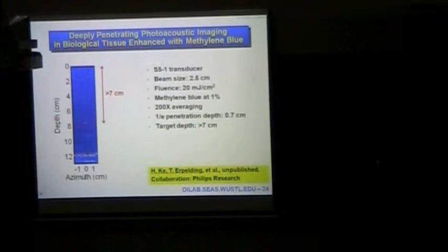There's this microscopic domain through photoacoustic tomography. Let me start with the acoustic resolution version. In the CT version of using photoacoustics, you're counting on math to reconstruct the image. Each transducer is unfocused. Here, we're using physics to form an image. The transducer will be focused.